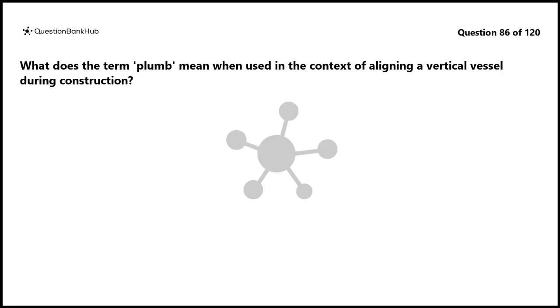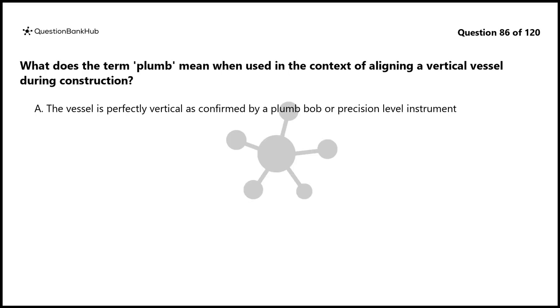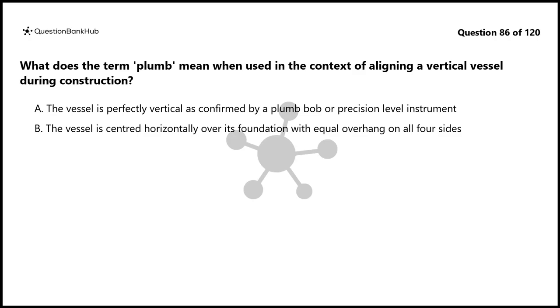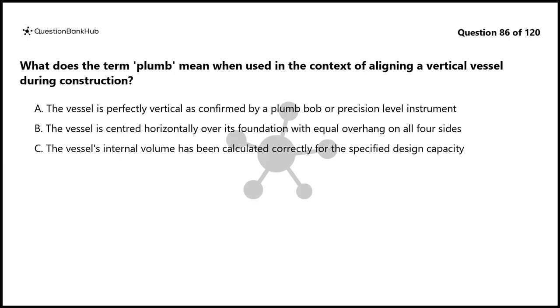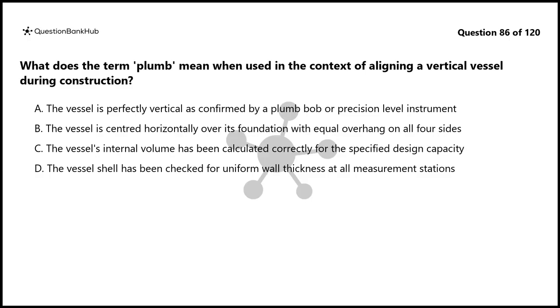Question 86. What does the term plumb mean when used in the context of aligning a vertical vessel during construction? A. The vessel is perfectly vertical as confirmed by a plumb bob or precision level instrument. B. The vessel is centered horizontally over its foundation with equal overhang on all four sides. C. The vessel's internal volume has been calculated correctly for the specified design capacity. D. The vessel shell has been checked for uniform wall thickness at all measurement stations.